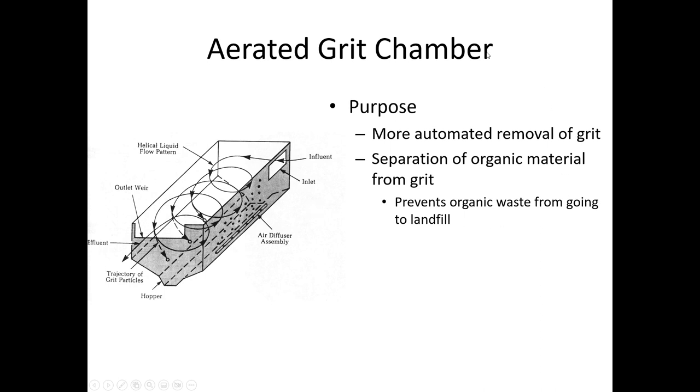And the other advantage of having an aerated grit chamber is that we want to ensure that the wastewater at no point becomes anoxic. Anoxic meaning that the dissolved oxygen of the water is so low that anaerobic bacteria begin to take hold. Because anaerobic bacteria will cause a lot worse odor than if the wastewater stays aerated. If it stays aerobic, then the odor is bad enough. But anaerobic and sulfur will begin to form hydrogen sulfide, which is a poisonous, corrosive, toxic gas. And so the aerated grit chamber can boost the dissolved oxygen levels up in the wastewater a little bit.